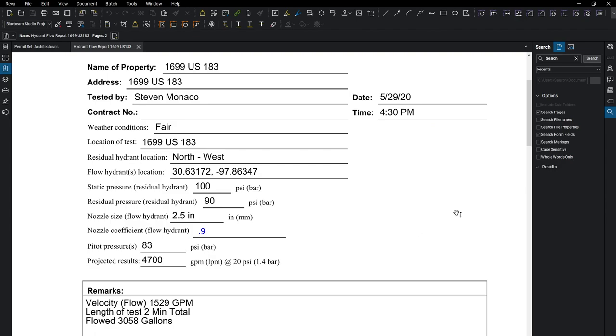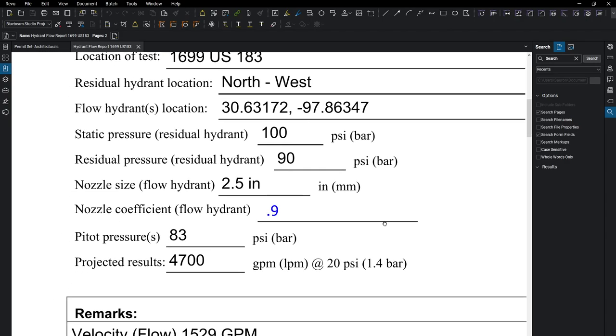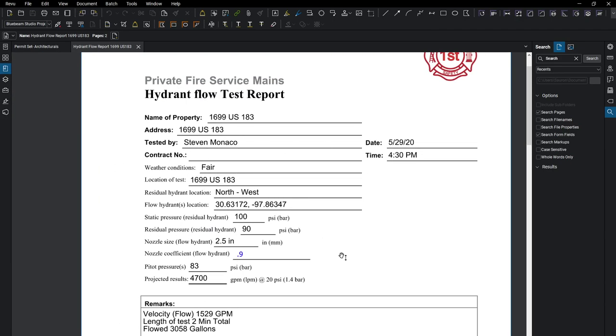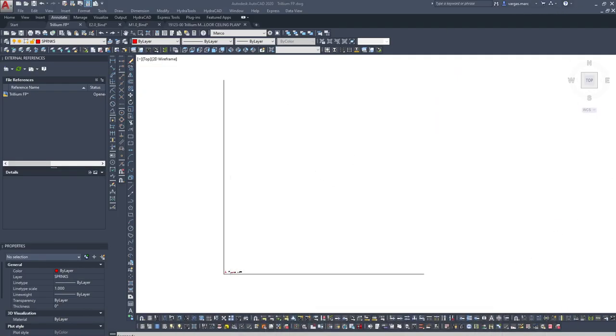We had a really good flow test on this one — static pressure of 100, only dropping 10 pounds, with a residual pressure of 90. That's a really good flow test and a perfect opportunity to use extended coverage sprinkler heads for the layout.